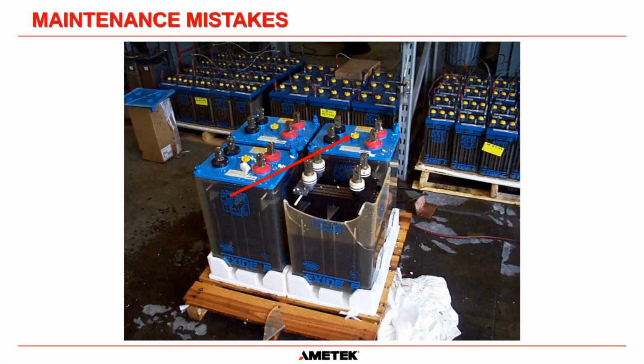This is what can happen. This is at, I can't remember where this is. This is at a warehouse where this whole battery string was being charged up. They'd probably been stored for 6 months and they were recharging it to maintain the charge. You can see the first mistake. They left the shipping vent plugs in the battery when they were charging them. They should have taken these off and put the flame arrestors on when they were charging them.